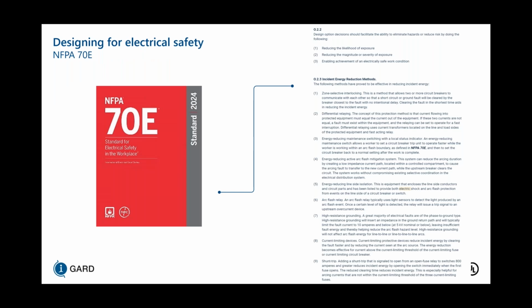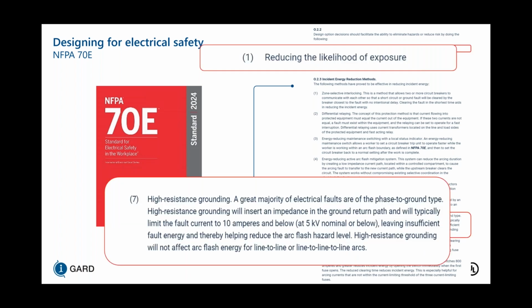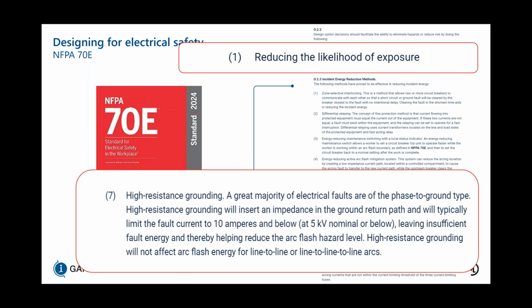Now, NFPA 70E, which is a standard for electrical safety in the workplace, indicates in Annex O.2.2 that design option decisions should facilitate the ability to eliminate hazards or reduce risk by doing the following: reducing the likelihood of exposure, reducing the magnitude or severity of exposure, and enabling achievement of an electrically safe work condition. So of the 9 incident energy reduction methods listed in Annex O.2.3, high resistance grounding is the only one that reduces the likelihood of exposure by placing this impedance in the ground return path at 10 amps or less on a system that's 5 kV or below. It leaves insufficient fault energy and thereby helps reduce the arc flash hazard level.